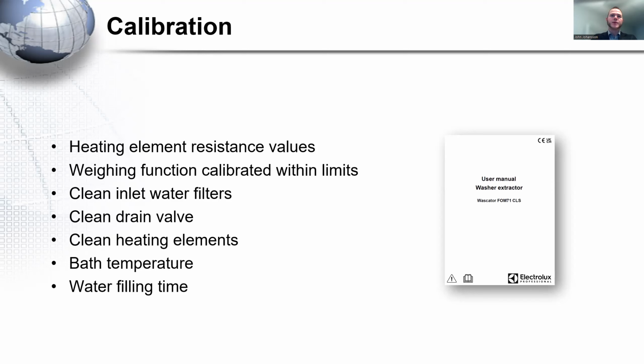The water filling time, there are also instructions in the user manual on how to check that, and it is a time stipulated that should be between 2 points in the program. When you fill the water, that should be within margins to make sure that you have the right pressure and you have clean inlet filters and so on. The last chapter in the user manual is about calibration of the machine. The user manual is delivered with every machine, but if you do not have it, just contact me or your local service partner and you will have it. I will also share it to the round-robin laboratories in the common folder. That is all for me. Any questions?